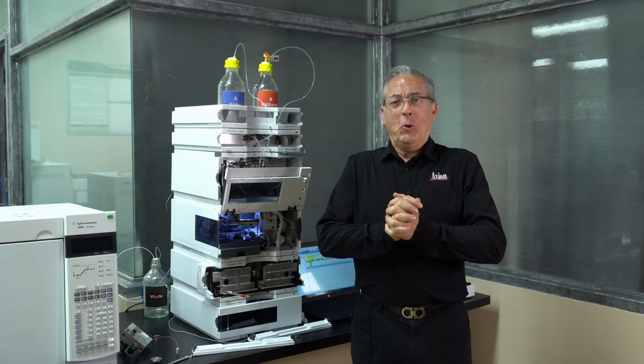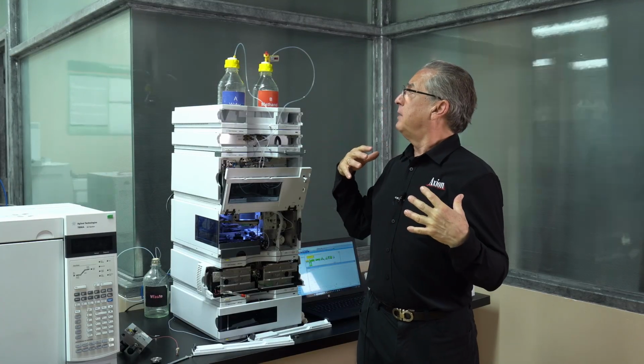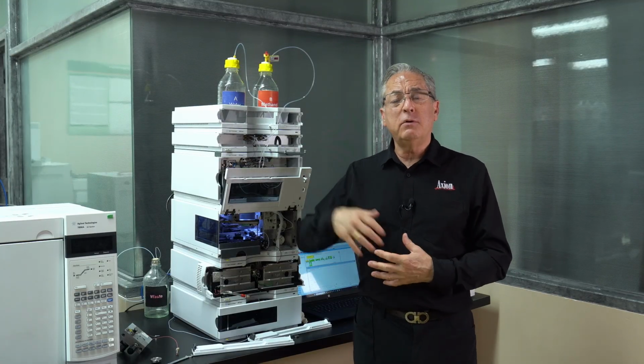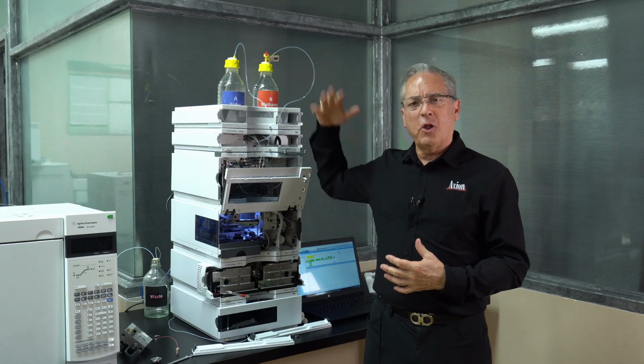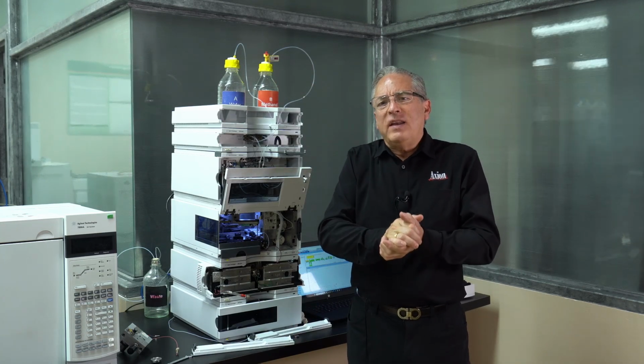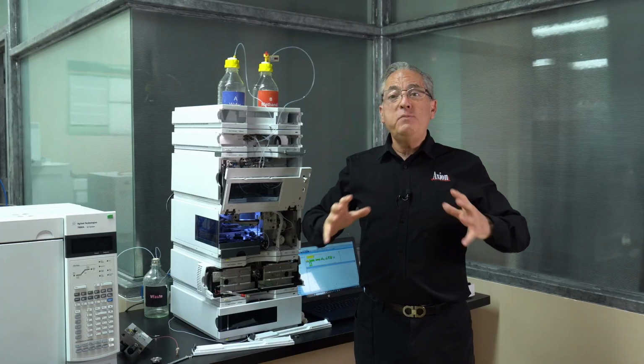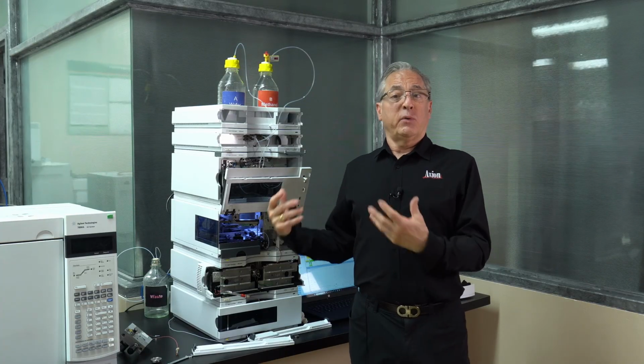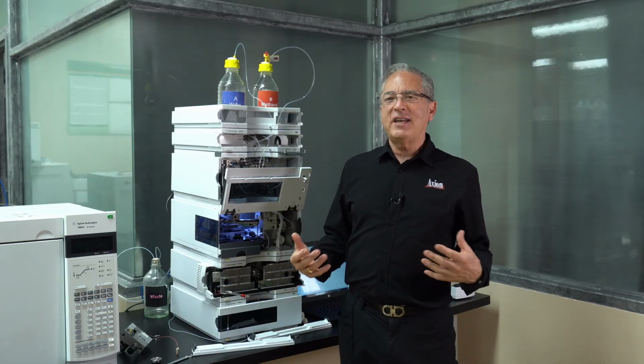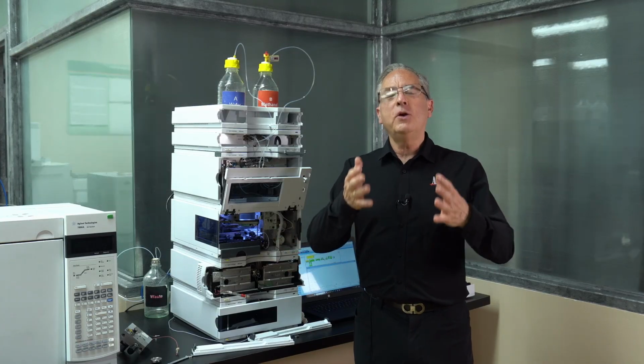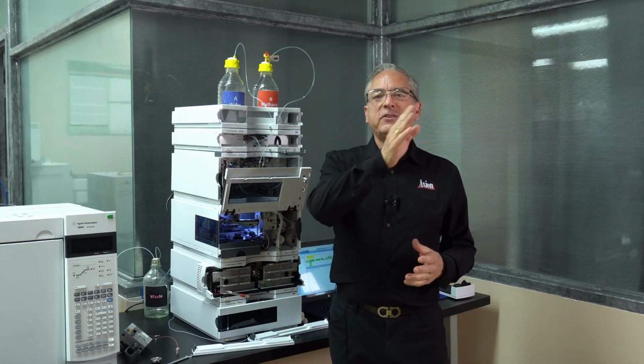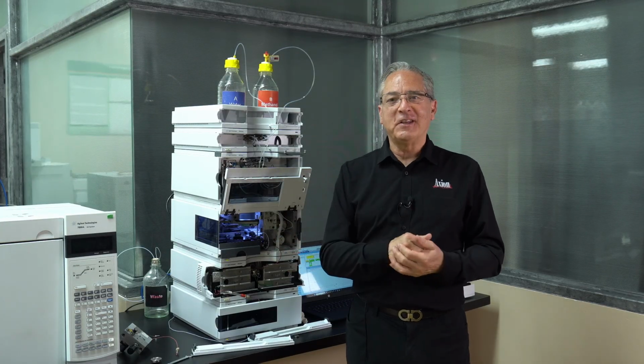So that is HPLC from top to bottom. We went through everything from the solvent bottles all the way down to the detector, and hopefully now you have a better feel for you being in control of the instrument. Yes, it requires maintenance, but the maintenance is not that difficult, and you can do it. So you could pump gas in your own car, you can change your own pump seals in HPLC.